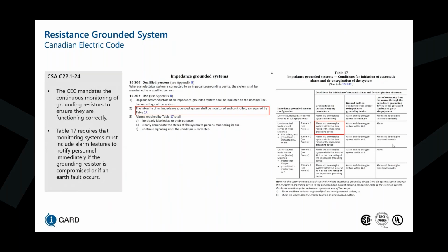Now our new relay, the Sigma 3C, is fully compliant with Table 17, including adding the 48-hour delay, and it can also detect a ground fault in an ungrounded system by picking up that neutral voltage elevation, and with the fact that we're not seeing any current at our CT due to the open circuit.